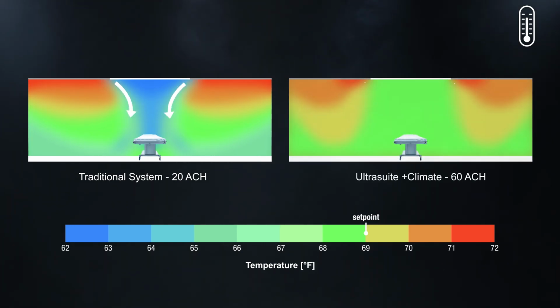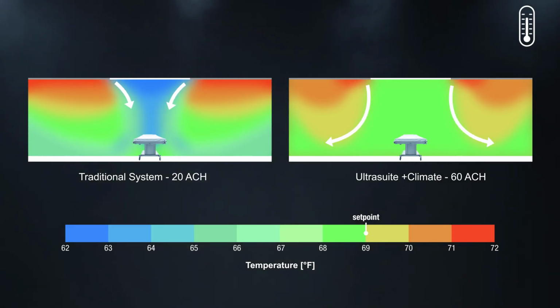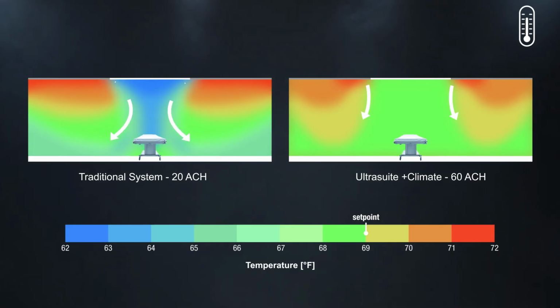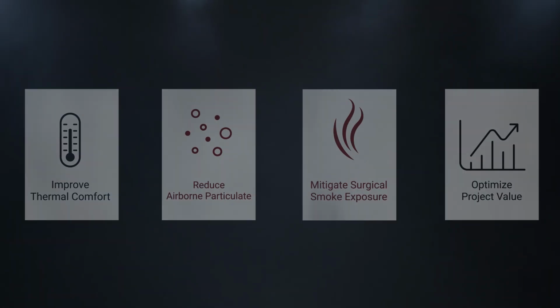At the higher rate of 60 air changes per hour, supply air is much closer to room temperature, resulting in a wider clean air column that creates a larger sterile working zone and more consistent temperatures throughout the room to improve thermal comfort for staff and reduce the risk of hypothermia for patients.